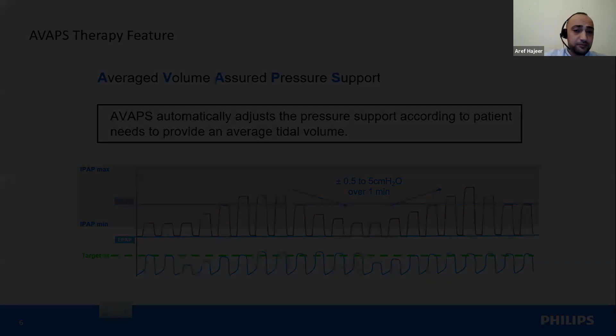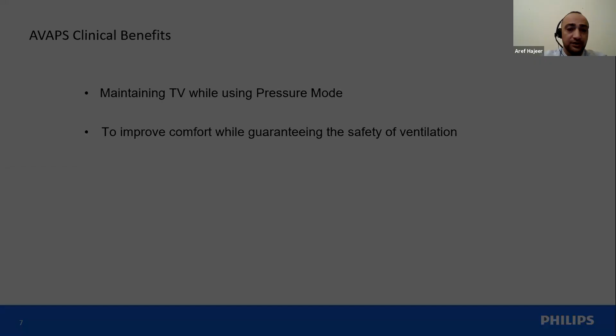The benefit of using the Avaps is maintaining the tidal volume while using a pressure mode, and this is an important one because if you use the pressure mode alone, you don't have any control on the tidal volume. Also, it can help to improve the comfort while guaranteeing the safety of the ventilation. How to set the Avaps? Normally we have this recommendation for setting the Avaps.